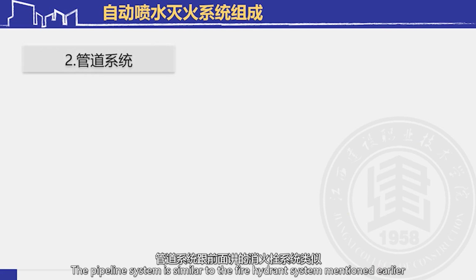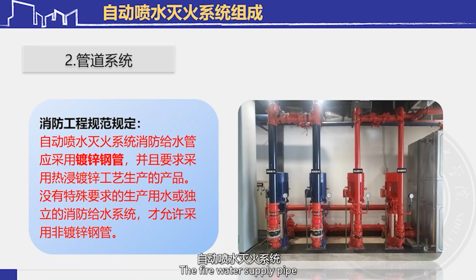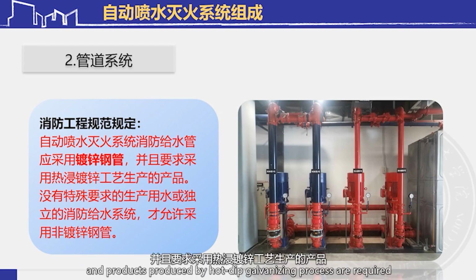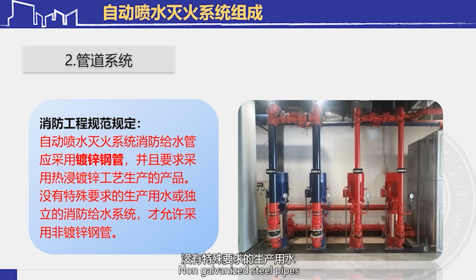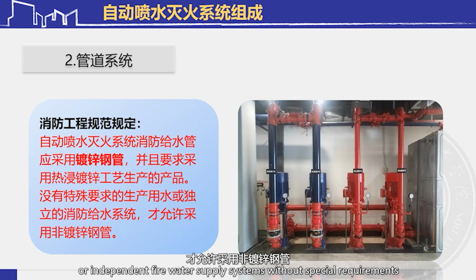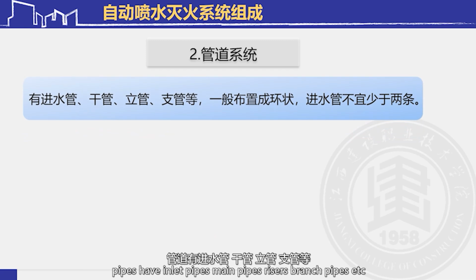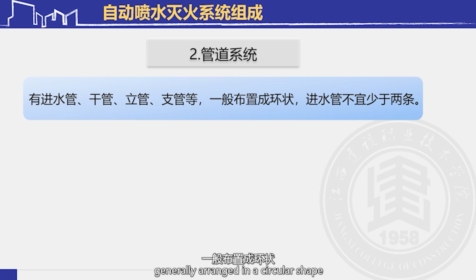The pipeline system is similar to the fire hydrant system mentioned earlier. The fire water supply pipe of the automatic sprinkler fire extinguishing system should be made of galvanized steel pipe, and products produced by hot dip galvanizing process are required. Non-galvanized steel pipes are only allowed for production water or independent fire water supply systems without special requirements. Pipes have inlet pipes, main pipes, risers, branch pipes, etc., generally arranged in a circular shape, with no less than 2 inlet pipes.